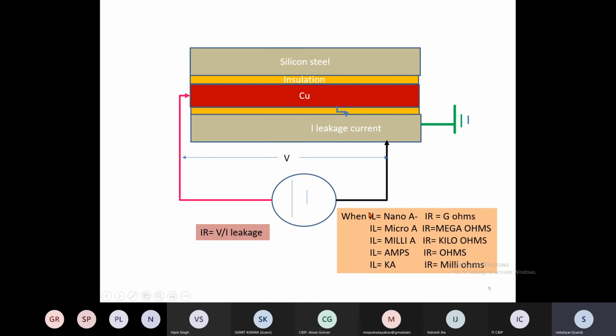So this is what happens when the insulation deteriorates from a very good insulating quality to poor insulating quality. And whenever this leakage current through the insulation increases to amperes or kiloamperes, we say that an electrical fault has occurred. Now, this silicon steel, if it is not grounded, these leaking electrons, because the silicon steel is mounted into the steel frame in the case of a transformer, motor or generator, will go to the human body and an electrical shock will be experienced.